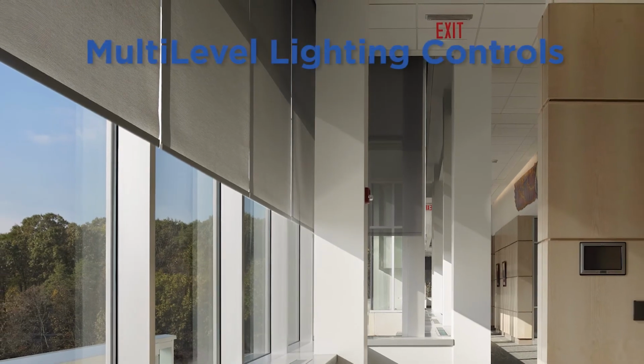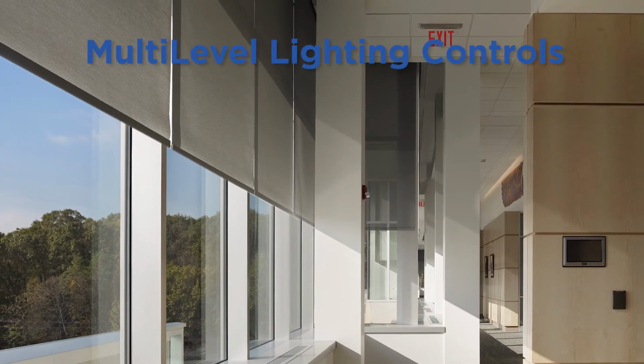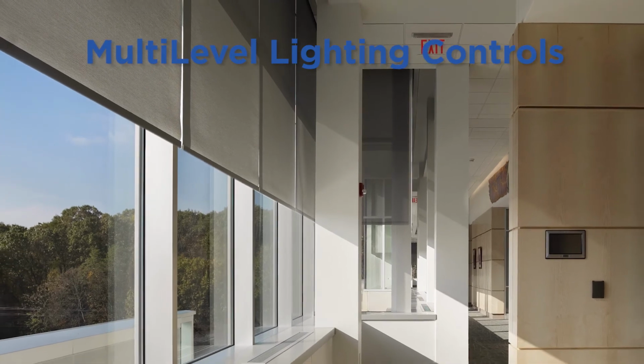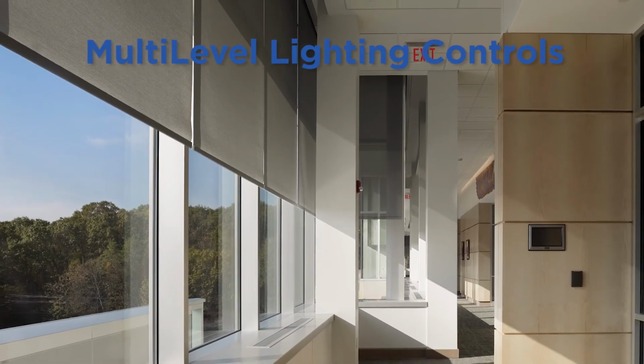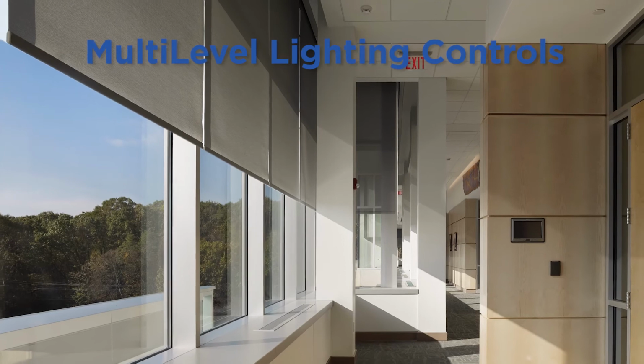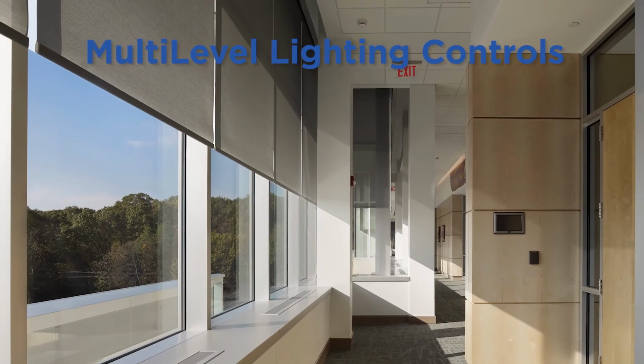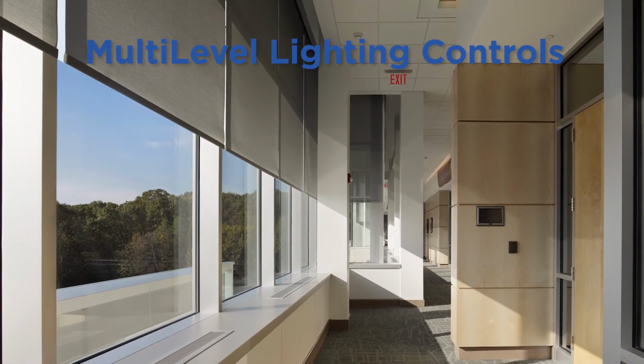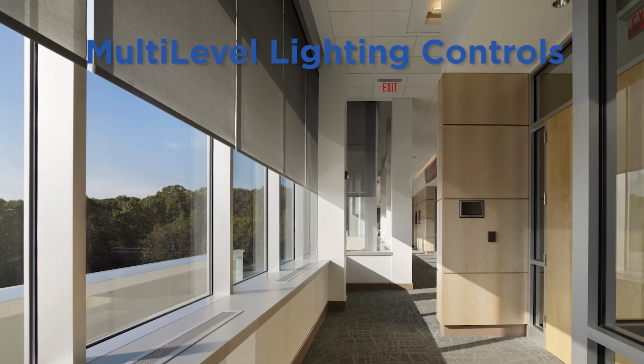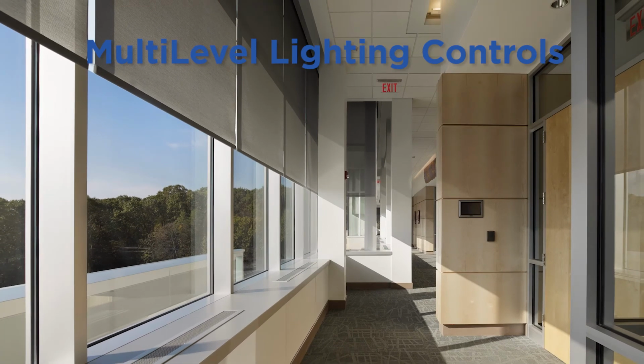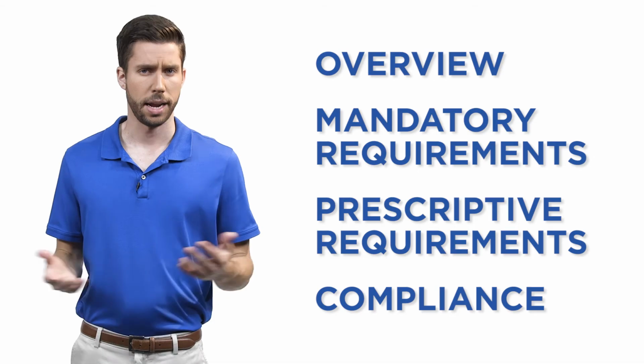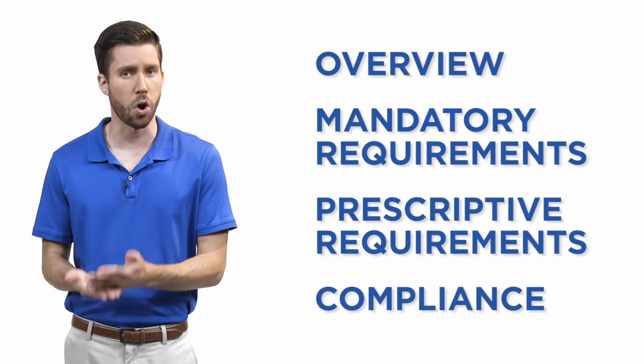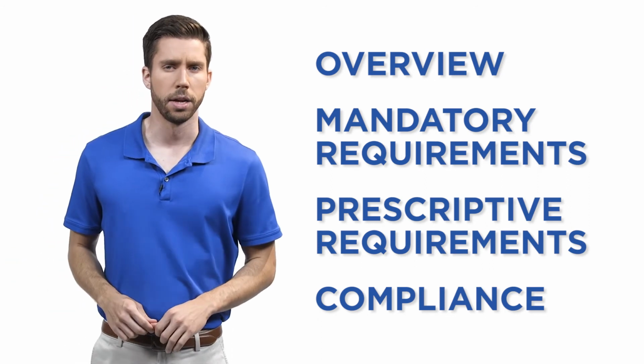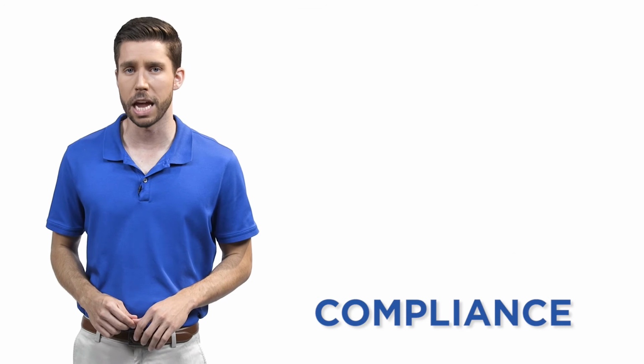Also, under the prescriptive requirements, automatic daylighting controls are required in secondary side-lit daylit zones. We'll talk more about this in Module 5 of this video series. But again, multi-level lighting controls are absolutely necessary to achieve compliance with this prescriptive measure.